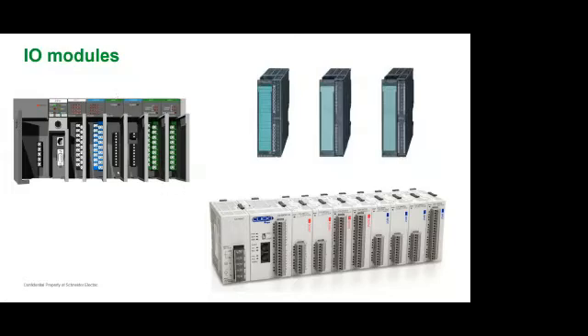And if you ask me whether all the PLCs will be in this format, no. You can also have a PLC with only input and output module. Those are called basic PLCs or modular PLCs. So they can perform limited operations with limited functions because they are very small, and around 4 or 10 IOs can be connected to them. But these types of backplanes you can use to connect more than 20-25 signals, and there are remote IO modules. From this, the Ethernet cable will run to a different place, and there you will have IO modules. You can connect to them, so they can be extended. The number of IOs can be extended to a certain limit.